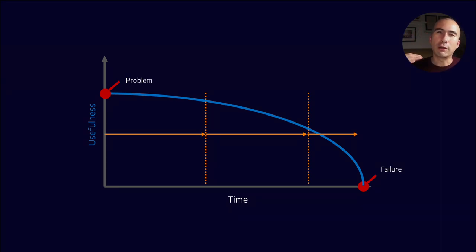Let me give you an example. Maybe you have a very slight shaft misalignment. As a result, you get an accelerating wear pattern. That problem event, so the problem to the failure, may be months, it may even be years. The P to F interval is very protracted. Let's say, for example, instead you installed the wrong bearing, and the tolerances are all off, and maybe there's shaft misalignment as well. Well, that P to F interval is going to be very short. Maybe it's in the matter of days.